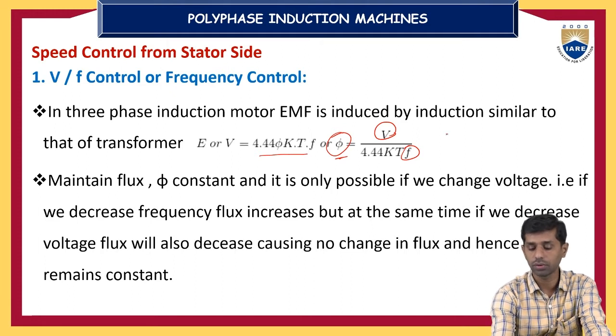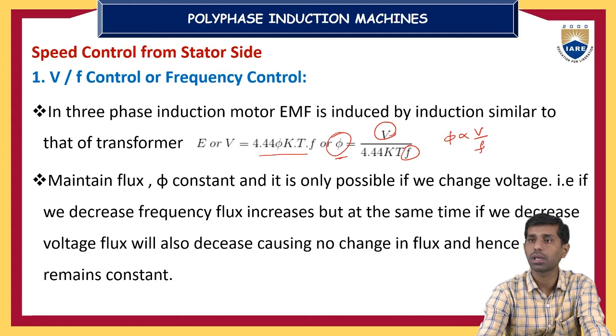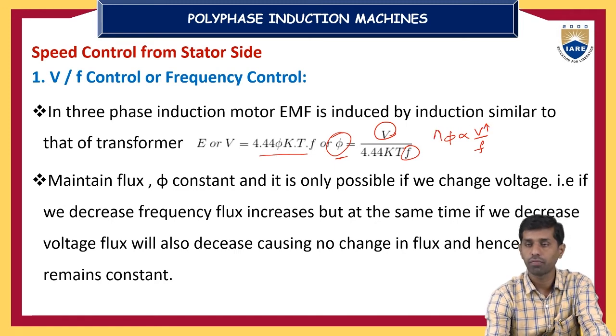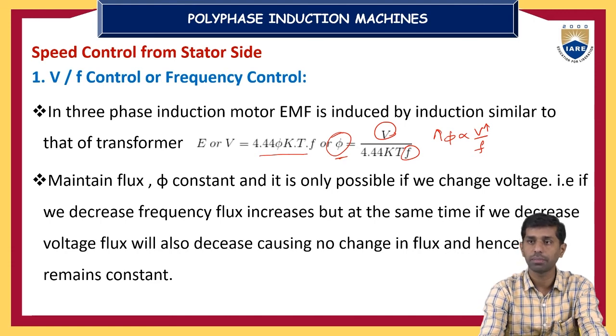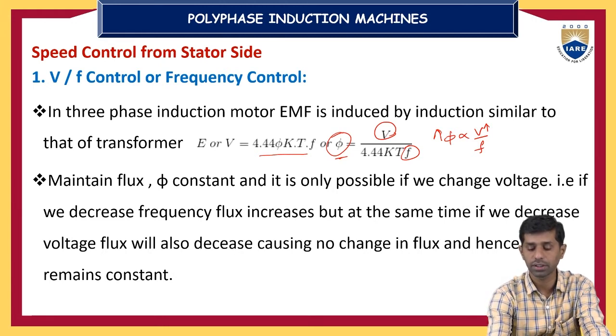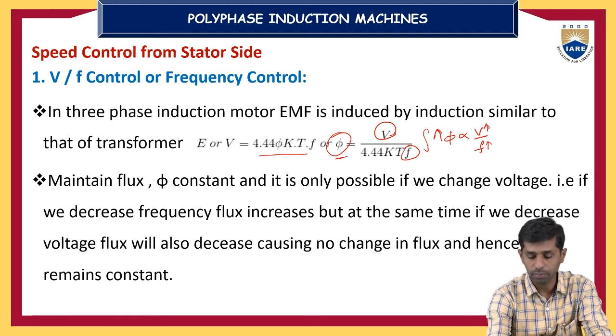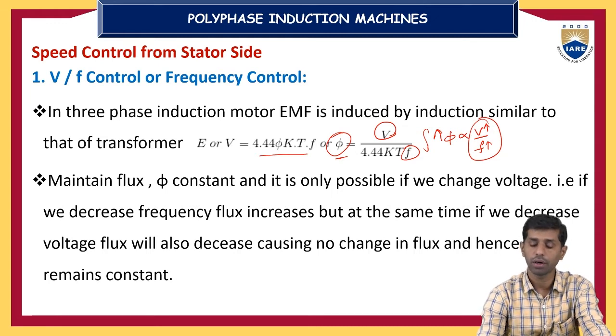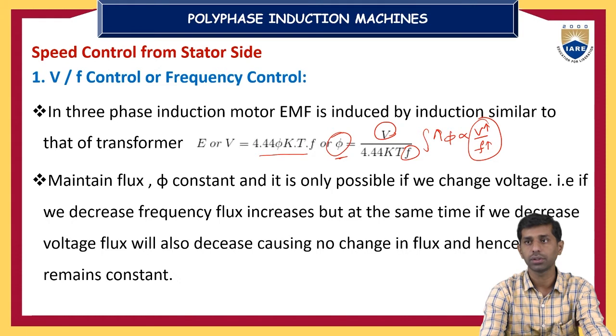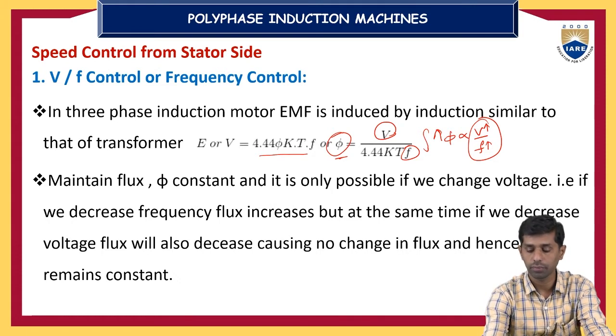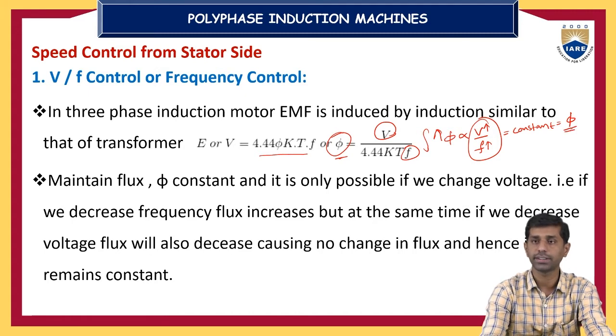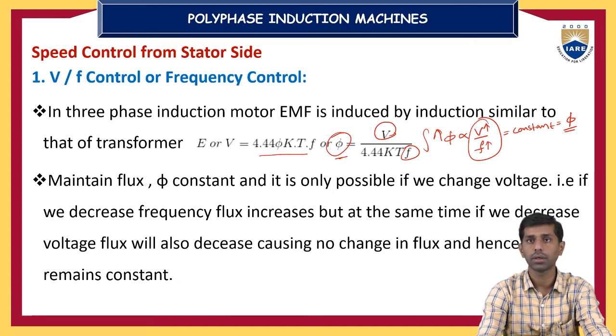Flux is directly proportional to supply voltage and inversely proportional to supply frequency. If you change only the voltage, flux increases, causing magnetic saturation in the stator and rotor circuits. If you increase only the frequency, flux reduces. So by maintaining the V/f ratio constant — decreasing voltage when decreasing frequency and increasing voltage when increasing frequency — the flux of the induction motor remains constant, giving good speed control results from the stator side.